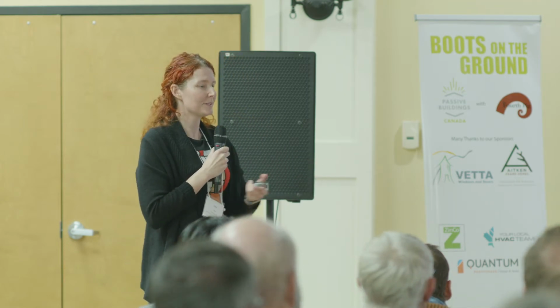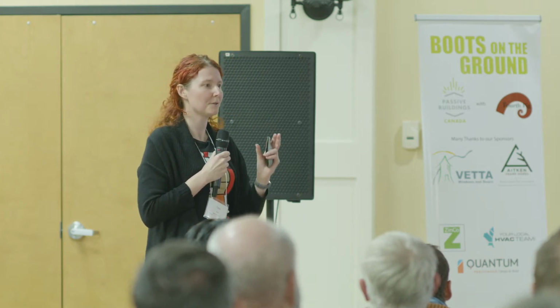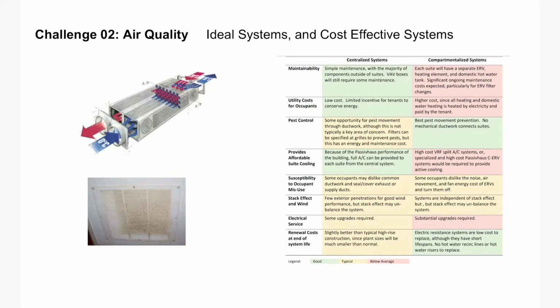When we first got the project, we were thinking we were going to use typical small ERVs. One of the challenges we quickly found was that at 250 square feet to 300 square feet per suite, these are almost all bachelors, there's very few ERVs, even in the Passive House field, that are small enough and have high enough efficiency. Another challenge that existed with fully compartmentalized systems was that we wanted to provide everyone with their own domestic potable water heating system, but the only ones that were available were electric. So we ended up with individual electric resistance heat providing the top up.